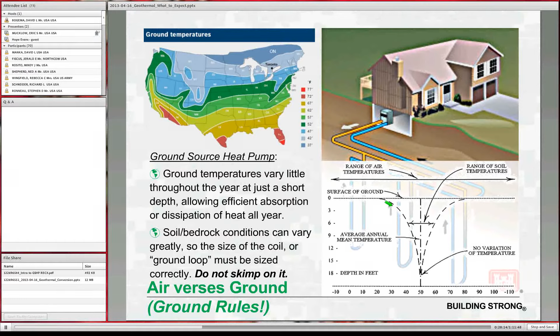So as you can see, if you just go down 18 feet, you're not getting a whole lot of fluctuation in the temperature below ground. And even if you're only at 4 feet if you're doing a horizontal, or 6 feet if you're doing a horizontal loop, you're only getting a plus or minus 10 degree swing rather than plus or minus 70 or 80 degrees. And most critically, you're staying above that 40 degree mark, where it gets too cool, or too hot for the air to be able to absorb heat that the air source heat pump is trying to dump into it during the hot weather.